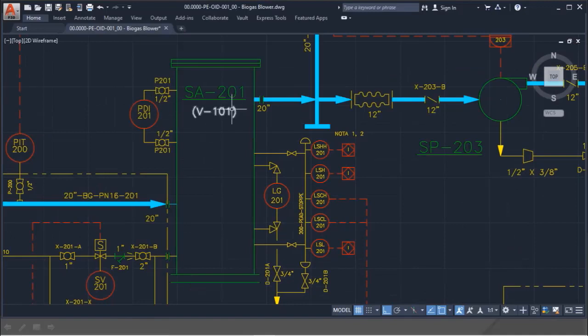This vessel should have a demister to prevent liquid particles from going to the blower. Because of that, we have a differential pressure indication in the field to verify if this demister is saturated. If it is identified that the pressure is very high, it's time to shut down the plant and do maintenance on the demister in order to decrease the pressure drop again.